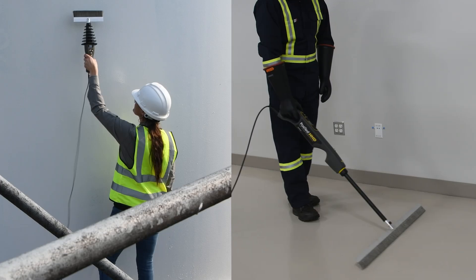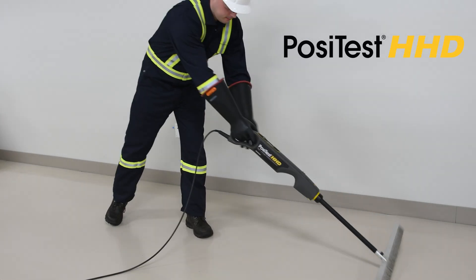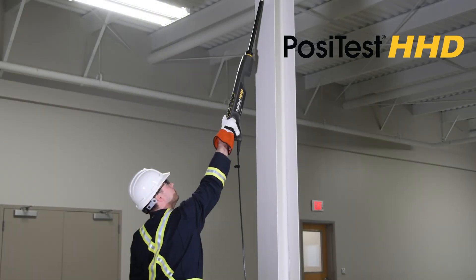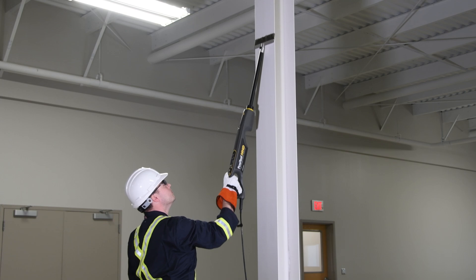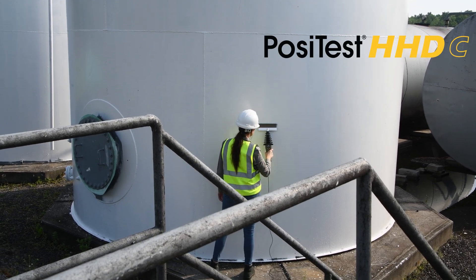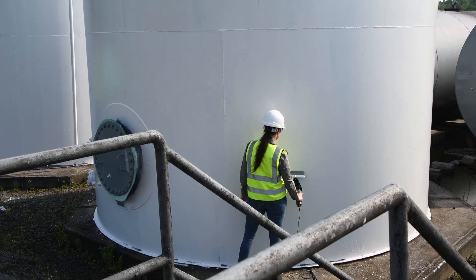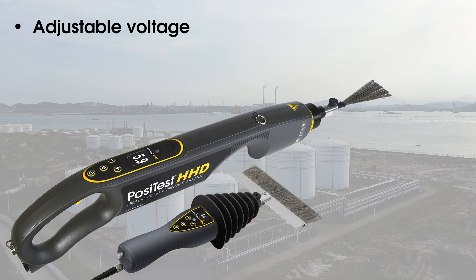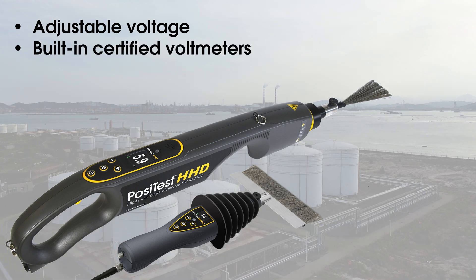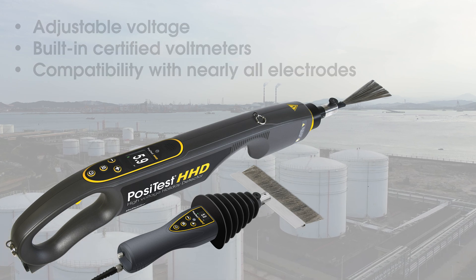DeFelsko offers two high-voltage holiday detectors. The PosiTest HHD features a stick design and uses Pulse DC technology to detect flaws. The PosiTest HHDC has a wand design and uses continuous DC to detect flaws. Both models feature adjustable voltage, built-in certified voltmeters, and compatibility with nearly all existing competitive electrodes.